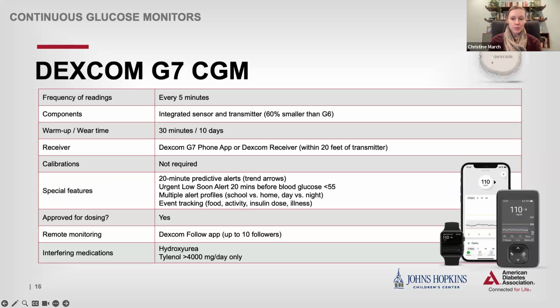Now, there are a few major differences between the G6 and the G7 from Dexcom. You still get readings every 5 minutes. However, now the sensor and transmitter are integrated into one piece, and the overall device is 60% smaller than the G6. You still wear it for 10 days, but now when you take it off, the whole thing can go in the trash. The warm-up period is shorter. It's only 30 minutes as opposed to 2 hours. There's no difference in the receiver options or in the recommendations for calibrations.